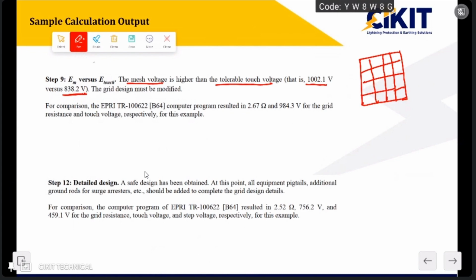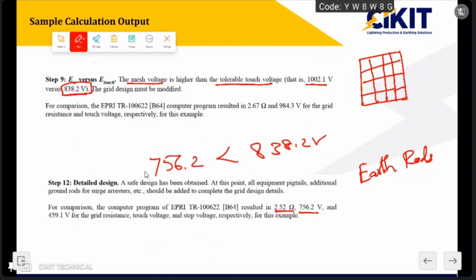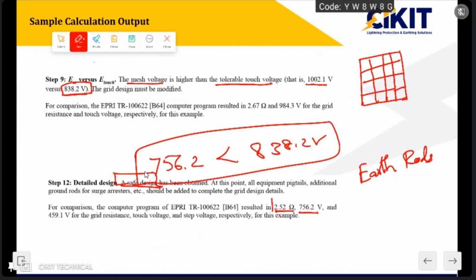The modification they did was to provide earth rods, for reducing the touch voltages. After installing earth rods, the values have been reduced. This is the result of the calculation after this modification. Here you can observe that the grid resistance value is 2.52 and the touch voltage is 756.2 volts, whereas the tolerable value is 838. So 756.2 volts is less than 838.2 volts, and hence the design is safe. They have concluded that a safe design has been obtained. In the safe design, if we closely observe, the resistance value is 2.52 ohm.